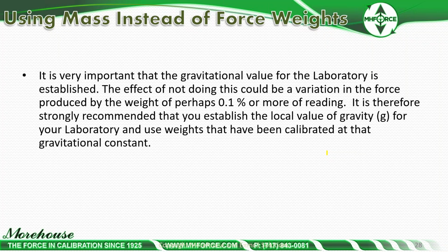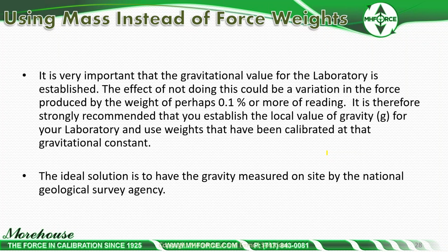So what he goes on to say is the effect of not doing this, of not correcting for the gravitational value, is a variation in the force produced by the weight of perhaps 0.1%. I just showed 0.1818% or more of reading. It is therefore strongly recommended that you establish the local gravity for your laboratory and use weights that have been calibrated at that gravitational constant. The ideal solution is to have gravity measured on site by a National Geologic Survey Agency.